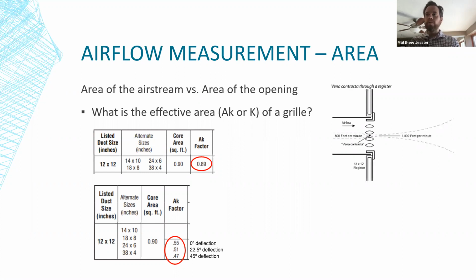Right off the bat, you can see as you start deflecting these grills, it affects the effective area of the grill and therefore your airflow measurement. It ranges from 0.55 down to 0.47. So for 2 different 12 by 12 grills, you can go anywhere from 0.89 down to 0.47, depending on the model and how the vanes are deflected. That can be a major difference in your airflow measurement. And I will point out that you can find these factors on the grill manufacturers' websites in some cases. I have not always been able to find them. And if you're just going into a building and going up to an existing grill, are you going to know the manufacturer and model number of that grill? Most likely not.